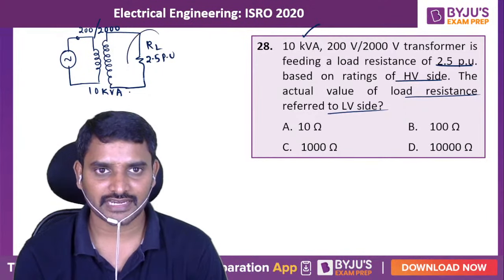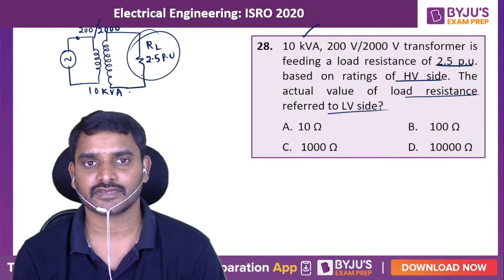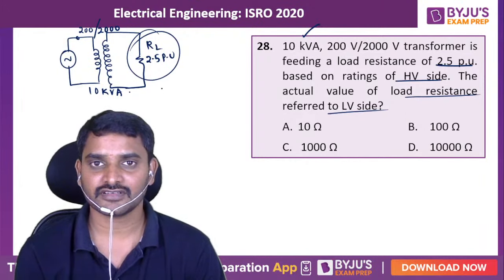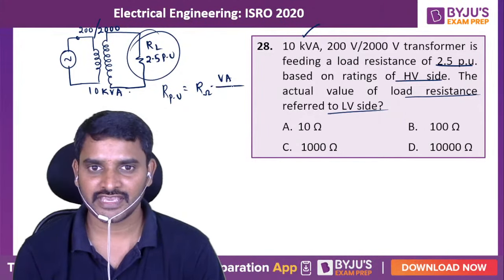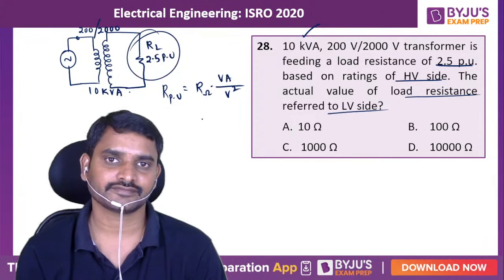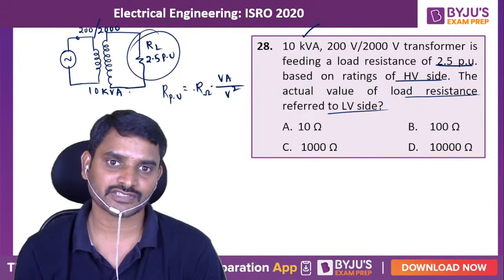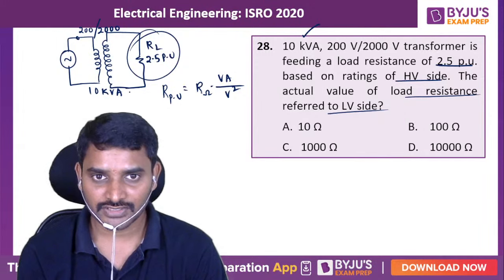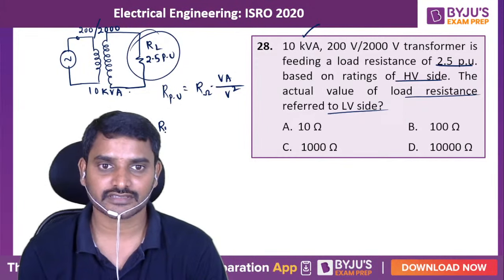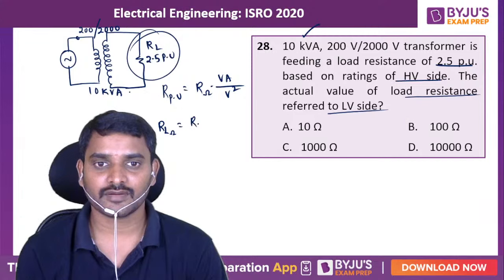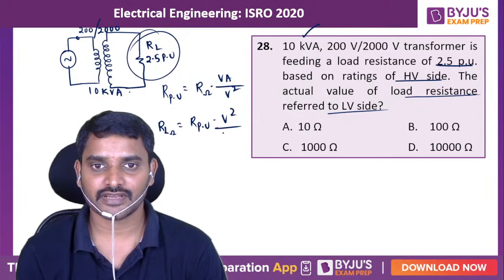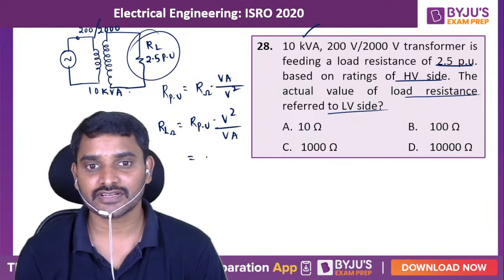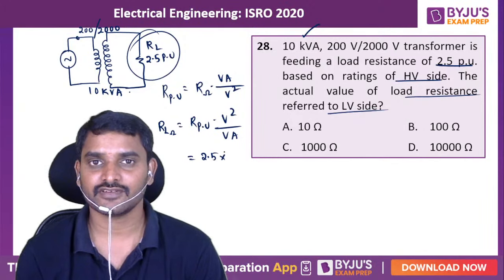So first of all, calculate the actual value of this load resistance. If you remember the formula of per unit resistance or per unit reactance, actual value into VA rating divided by voltage square. So you substitute VA rating divided by voltage square, you will get the answer. I need actual value. So this is the actual value of load resistance. So I will get R per unit into V square divided by VA. What is the per unit resistance? He has given 2.5. What is the voltage? Operating voltage on this side, this is 2000.